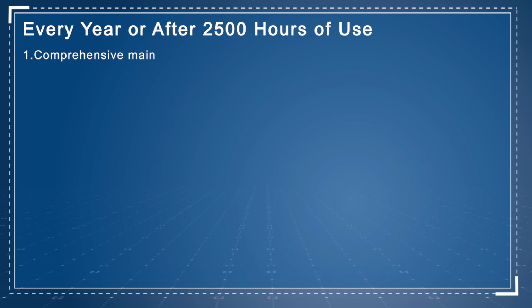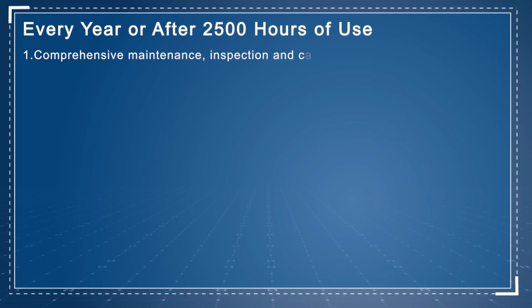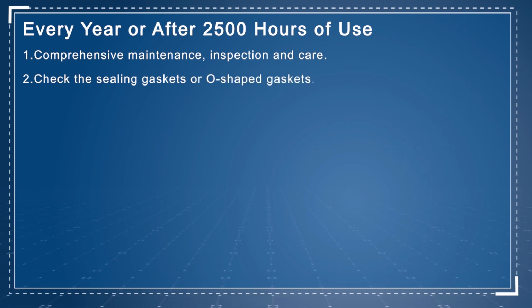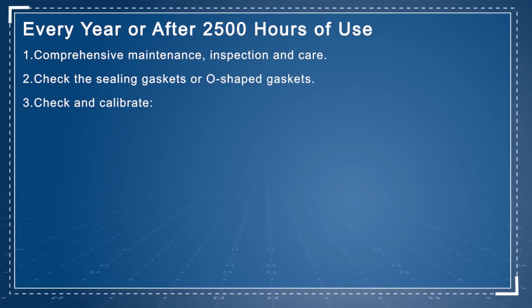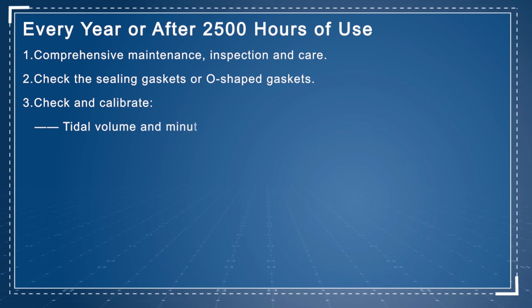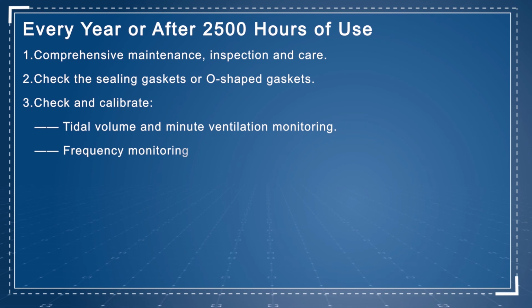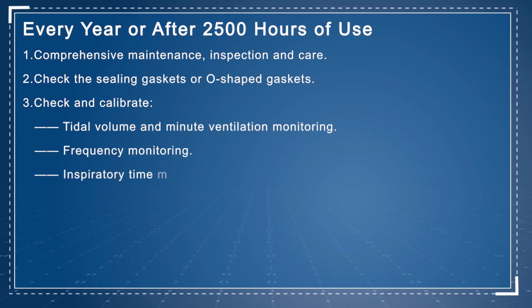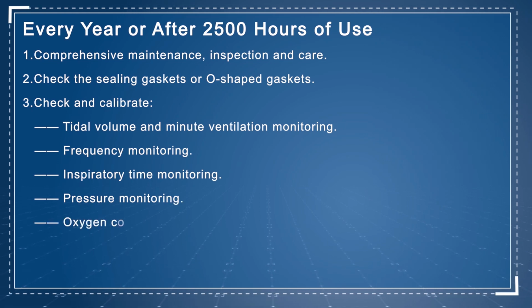Every year or after 2,500 hours of use. 1. Comprehensive maintenance inspection and care. 2. Check the sealing gaskets or O-shaped gaskets. 3. Check and calibrate tidal volume and minute ventilation monitoring, frequency monitoring, inspiratory time monitoring, pressure monitoring, and oxygen concentration monitoring.